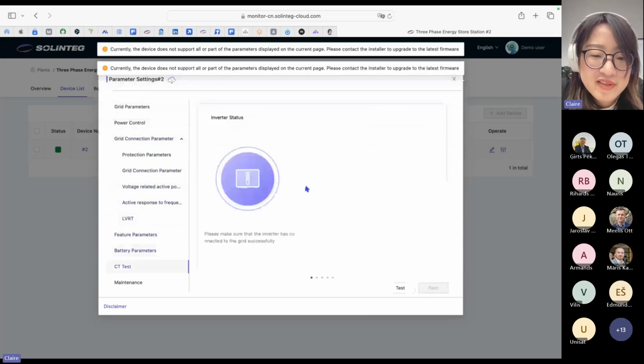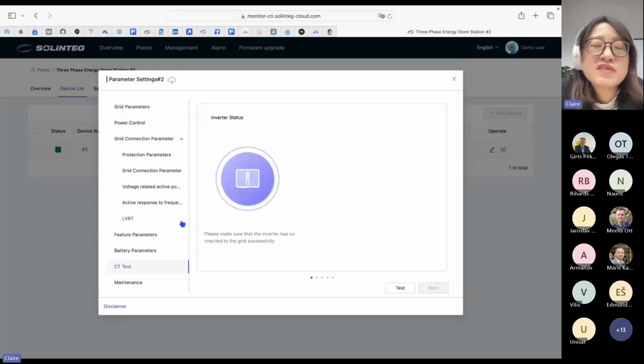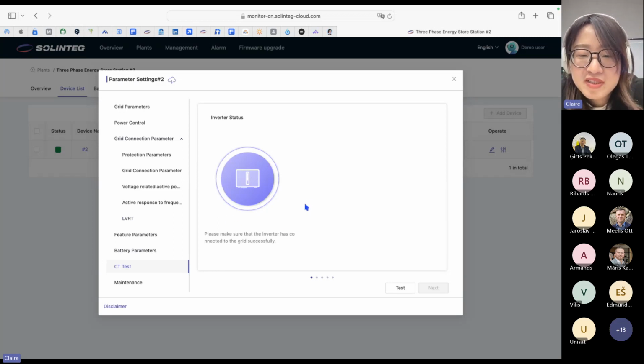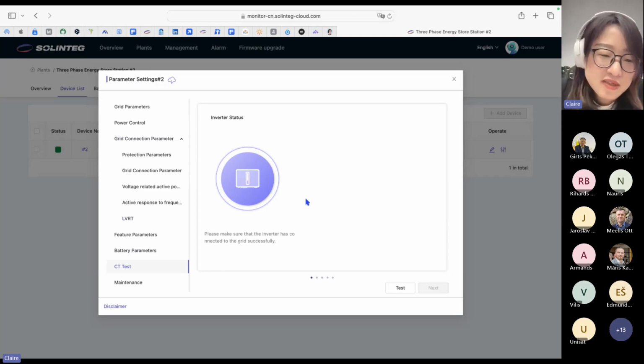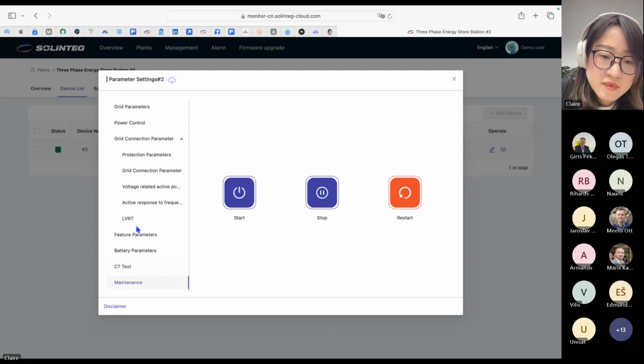And we also support a test function, because in a hybrid system we noticed that many installers make mistakes on the CT installation. Sometimes they connect the CT's phase in the wrong phase, or sometimes they install the CT in the wrong direction. So these are very normal mistakes made by installers. So we have this function. We can help the installer to detect if their CT is connected correctly. And we can also remotely start or stop the inverter.